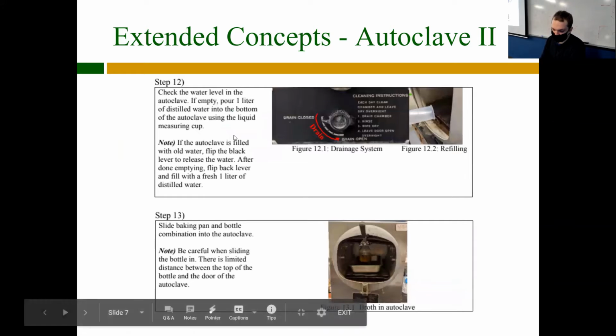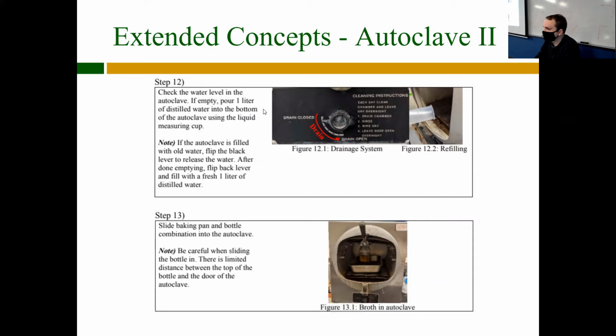Step 12 in the instruction manual is to check whether the water level is okay. You want at least 1 liter of water in there—you can go a little over, but not under, or the autoclave will shut off halfway through its procedure and you'll have to start over. It needs enough water to reach proper pressure.